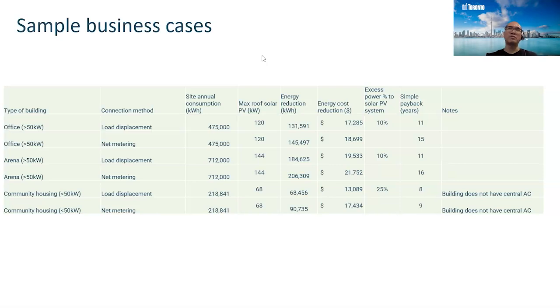Most of the time, the biggest problem is the inverter—they fail over time. 12 years is the number we find where they'll fail, and we actually put an inverter replacement cost in the business case at year 12 to replace them. Some fail sooner, some last longer, it depends. The interesting thing is if you go online and look at the inverter manufacturers, they always give you a warranty of 12 years—and there's a reason why they do that, because after 12 years, they fail.